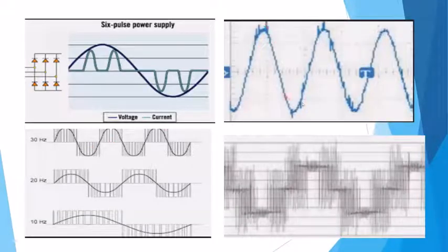So again, you get these extra jags, and this is what we're worried about: keeping that original generated power that was out there controlled so that we do not create other issues. I've done a lot of plastic machines. I've seen this 3rd, 5th, 7th harmonic actually create pulses and noise, and actually radio noise. It'll actually affect the color feeders into motors, into the molding machines. It'll change telemetry. It'll damage other electronic devices. So power quality is important.